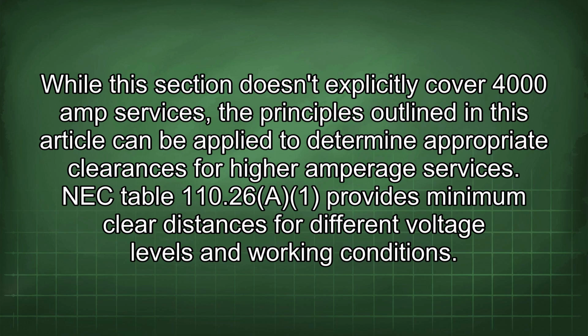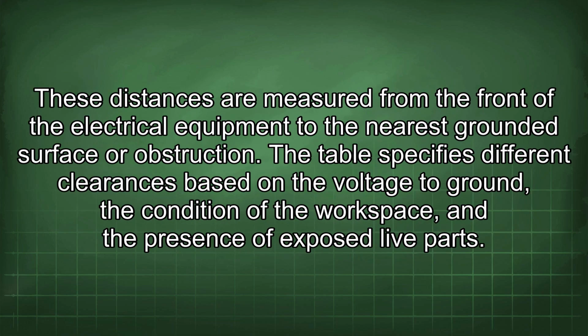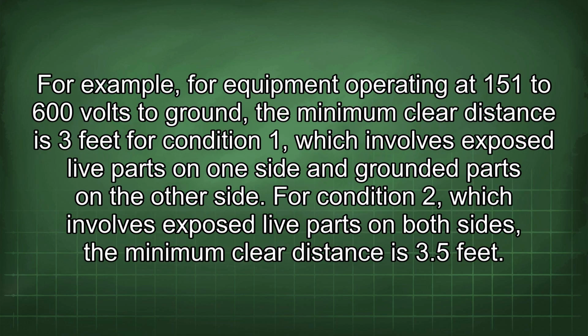NEC Table 110.26 provides minimum clear distances for different voltage levels and working conditions. These distances are measured from the front of the electrical equipment to the nearest grounded surface or obstruction. The table specifies different clearances based on the voltage to ground, the condition of the workspace, and the presence of exposed live parts. For example, for equipment operating at 151 to 600 volts to ground, the minimum clear distance is 3 feet for condition 1, which involves exposed live parts on one side and grounded parts on the other side.